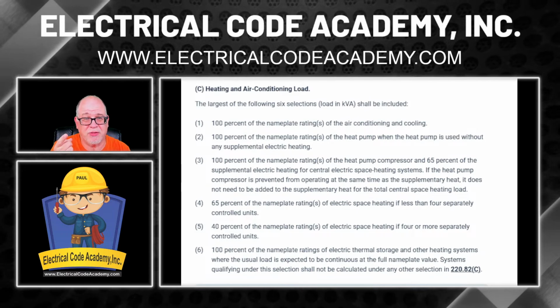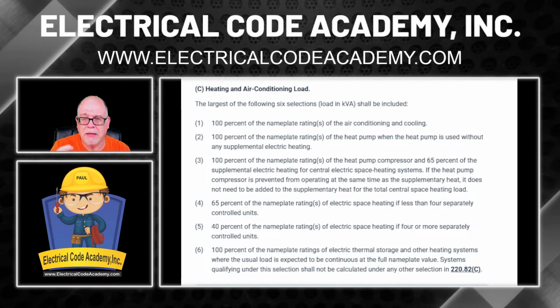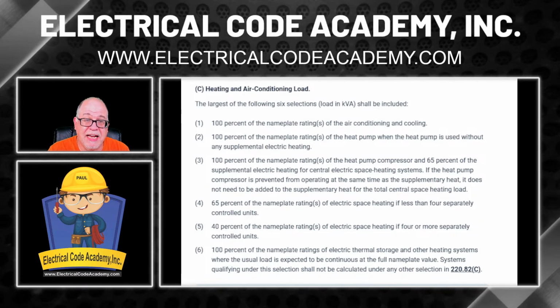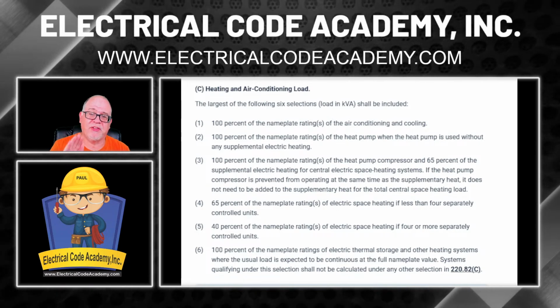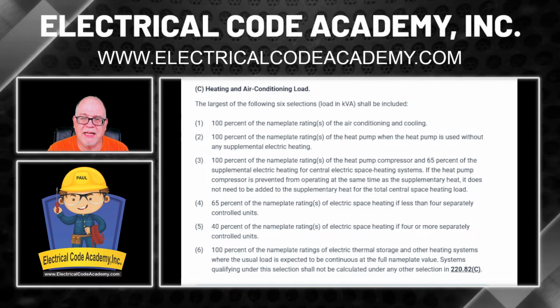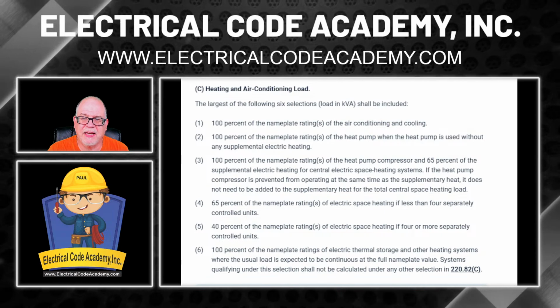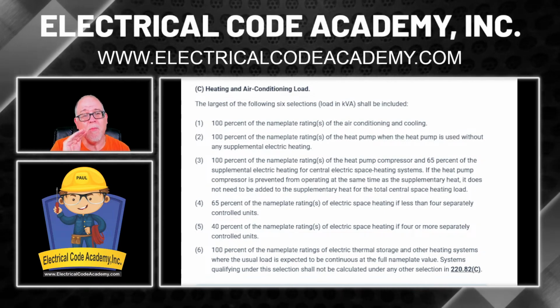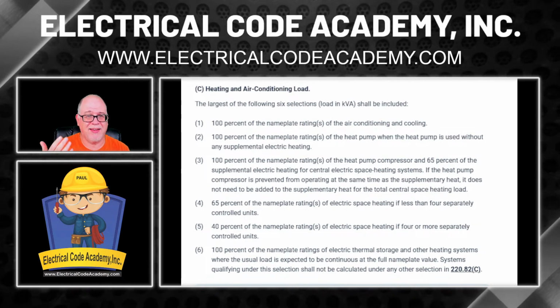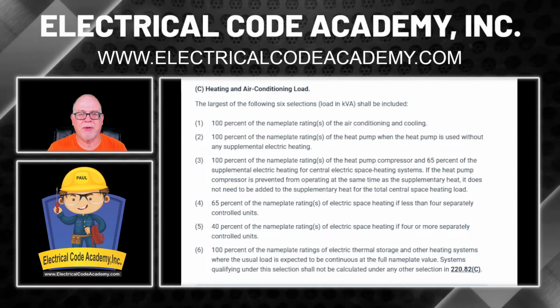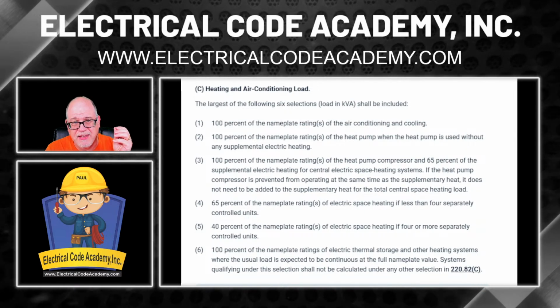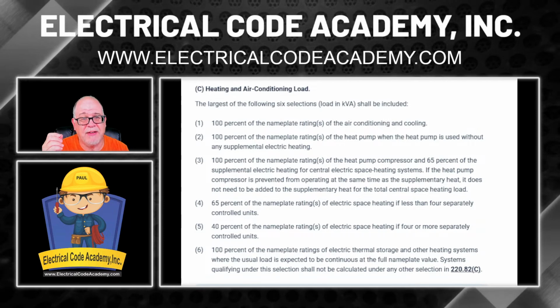We had 6, remember? So then we have number 5. Number 5 says 40% of the nameplate rating of electric space heating if there are 4 or more separately controlled units. We had 6. So obviously, we're going to be comparing number 1 for AC versus number 5 for the heat.